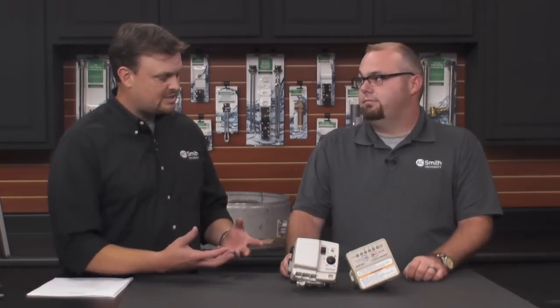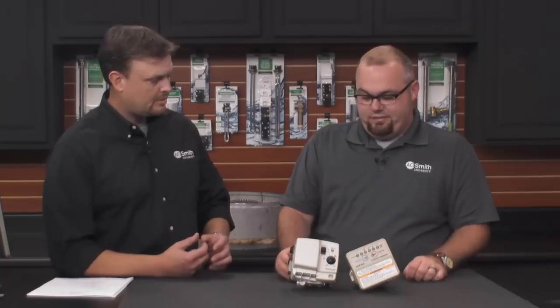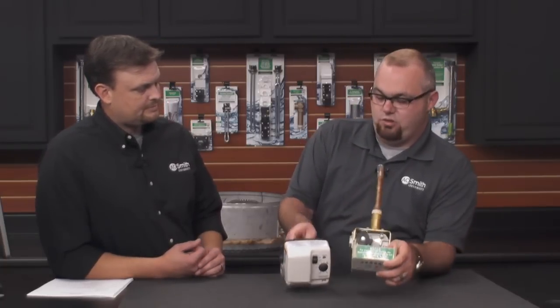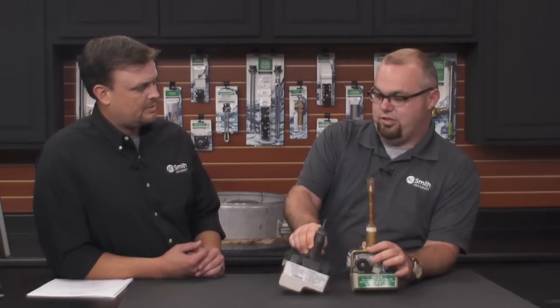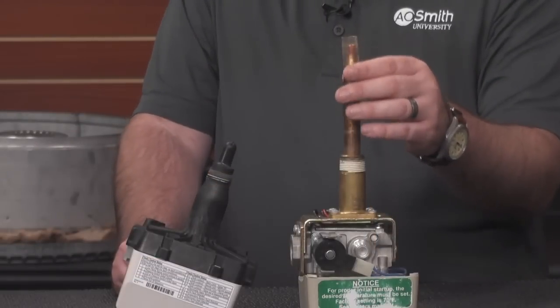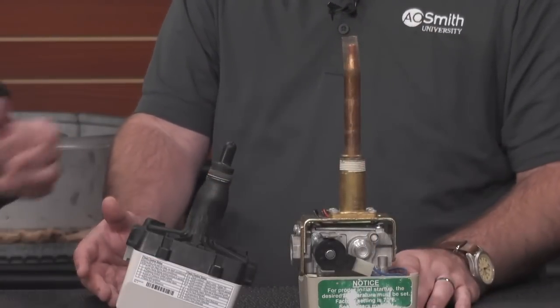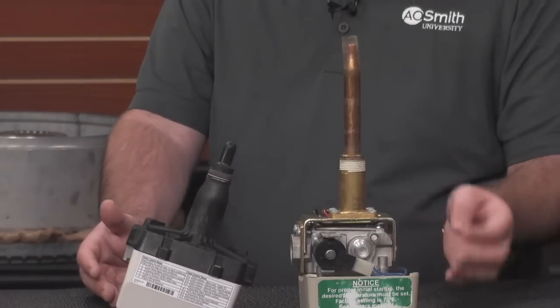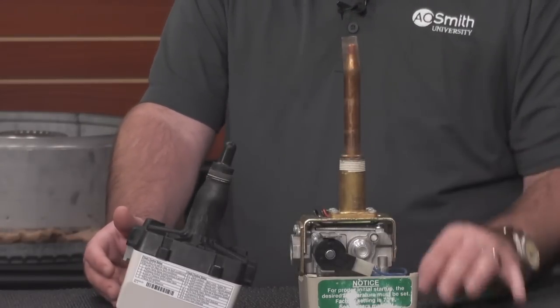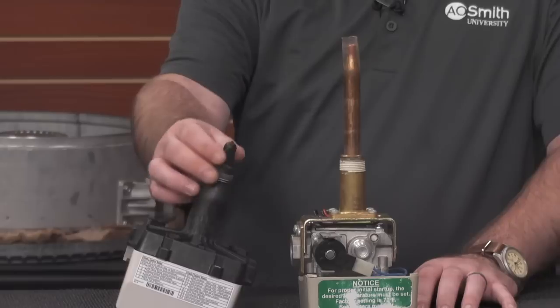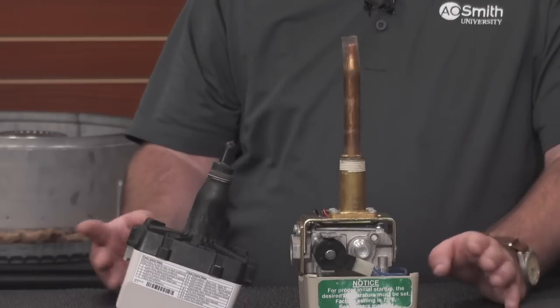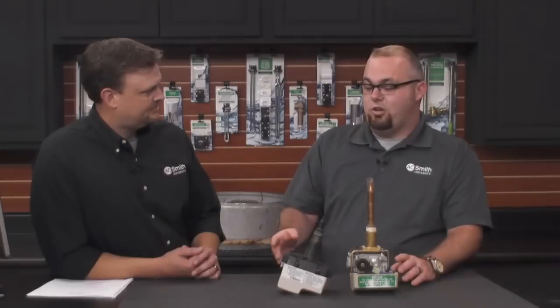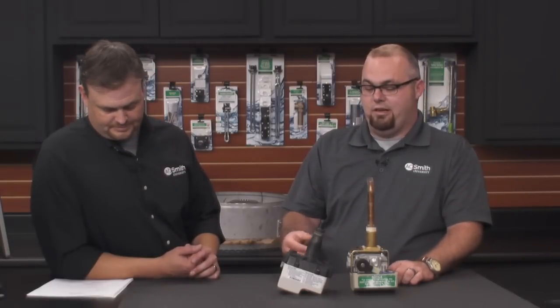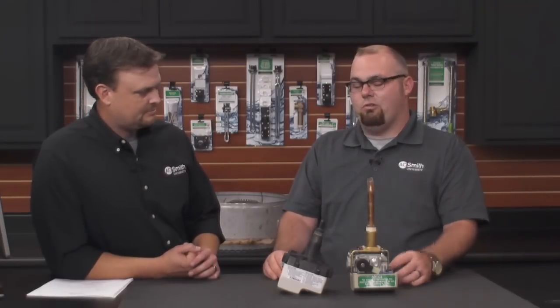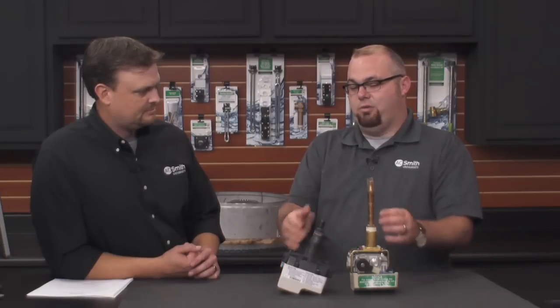Is the way we sense temperature any different? Both of these control valves use thermistors. They're just encased in a different type of probe. The IntelliVent valve uses a copper probe like old school mechanical valves. It looks like a rod and tube probe, but it actually has a thermistor in it. The Honeywell has a thermistor also. So they both control temperature very accurately because they use a thermistor. It's a lot better than a rod and tube style, but they are both using thermistors.